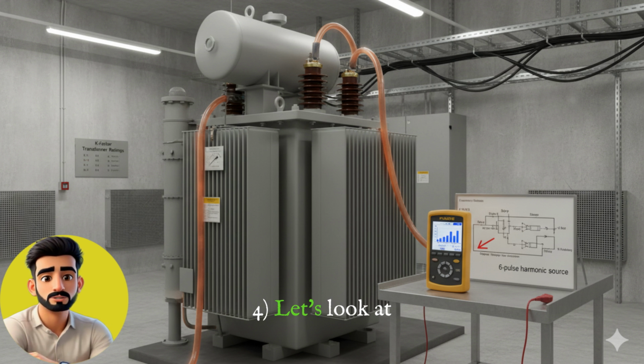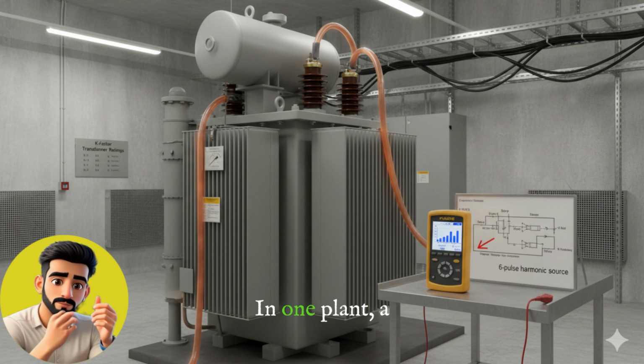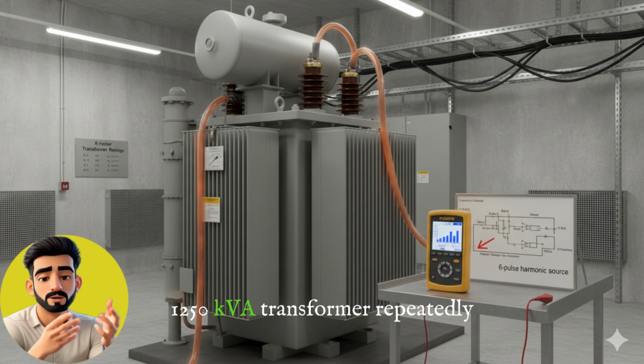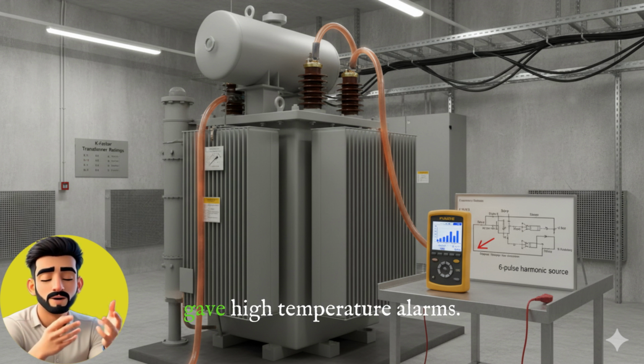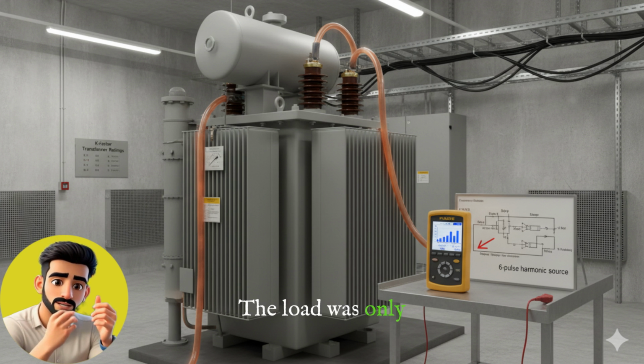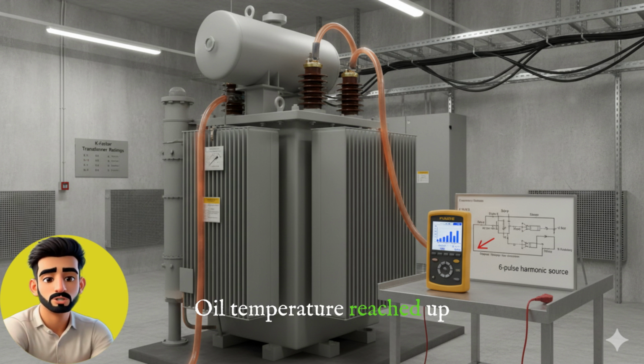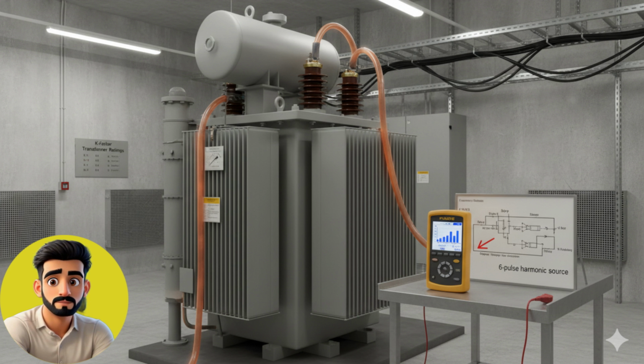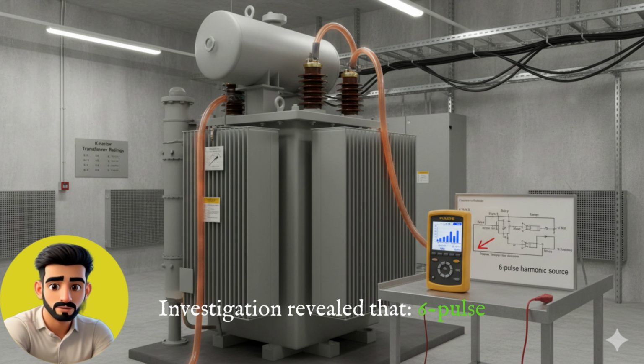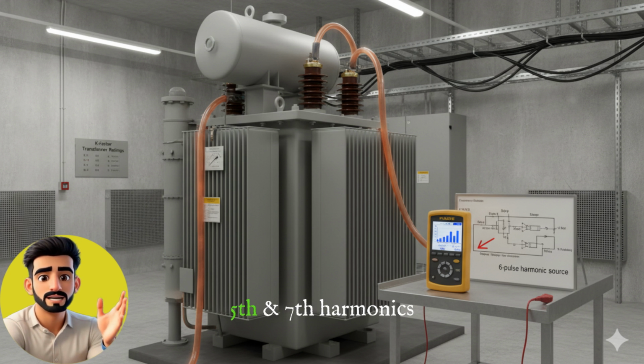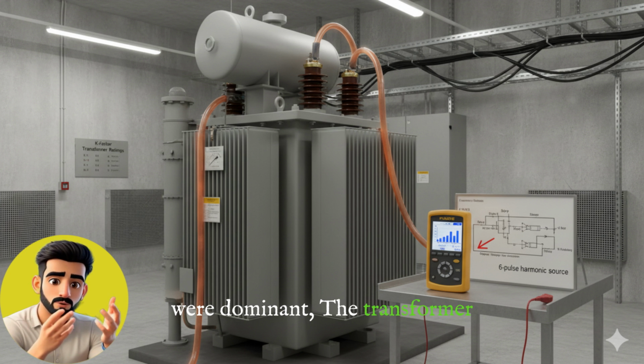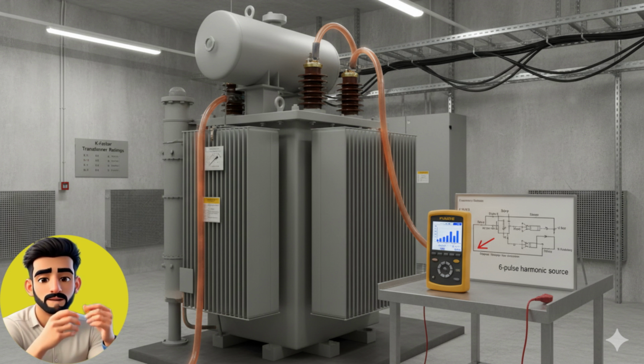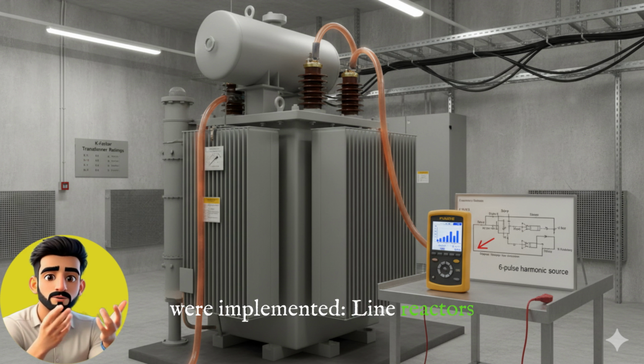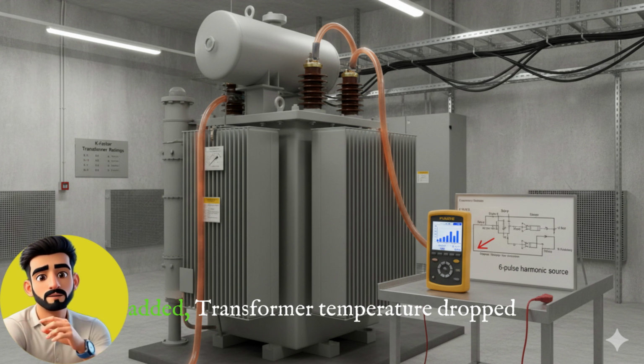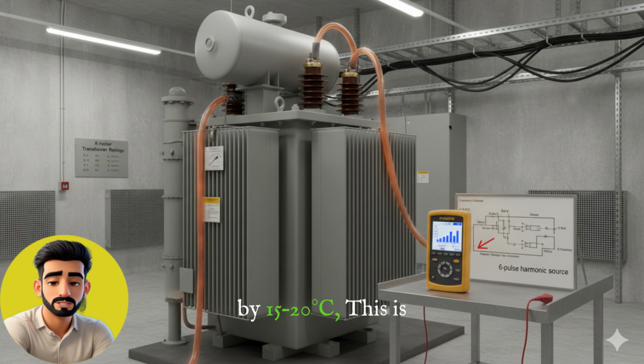4. Let's look at a real plant example. In one plant, a 1250 kilovolt ampere transformer repeatedly gave high temperature alarms. The load was only 55%. Oil temperature reached up to 75 to 80 degrees Celsius. Investigation revealed that 6 pulse drives, high THD, and 5th and 7th harmonics were dominant. The transformer was a normal K1 type. Let's see what solutions were implemented. Line reactors were installed, a passive harmonic filter was added, and the transformer temperature dropped by 15 to 20 degrees Celsius. This is the real impact of harmonics.